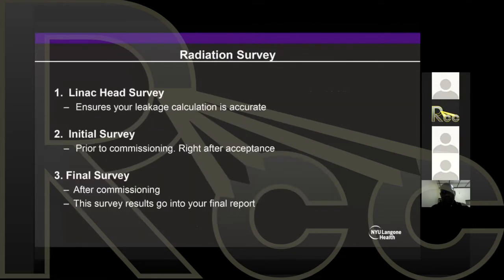Okay, so we're going to get to the fun part. We're ready to do a radiation survey. We're going to need to do 3 measurements. For a new piece of equipment, the first one you do is a Linac head survey. This is to ensure your leakage calculation is accurate. Then you do an initial survey prior to commissioning, probably right after acceptance. In this one, you don't need to have your output right on. You just need to make sure that everything is good for you to be doing commissioning. You're going to be using the beam for a long time during commissioning, so you need to make sure your shielding is good. And again, when you're completely done with your commissioning and you have your output perfectly tuned, you do a final survey, and this is the one that goes to your final report.